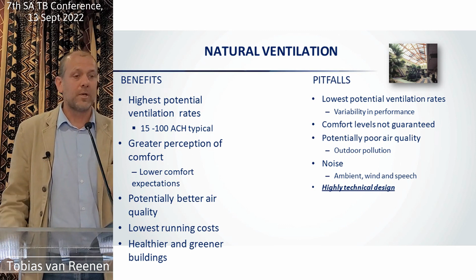Okay. But let's just use a back of the cigarette box ventilation calculation for natural ventilation. The building regulations in South Africa say that our windows must be greater than or equal to 5% of the floor area. So for that same 100-person waiting room, that gives us that many square meters of wall area for a single wall. Assuming a light breeze, I'm from Pretoria, a very windstill part of the country. On a quiet day when you can't see the trees moving, it's about 1 to 2 meters per second. It's a very, very light breeze. In those conditions, through that window, we come out at about 2,438 liters per second for that waiting room.